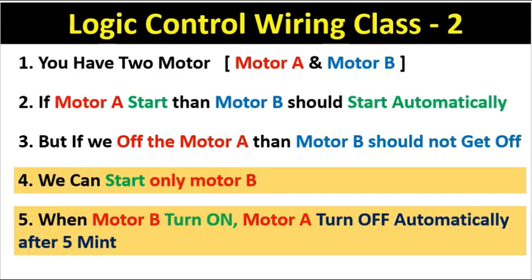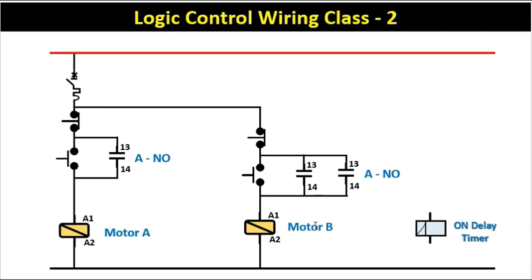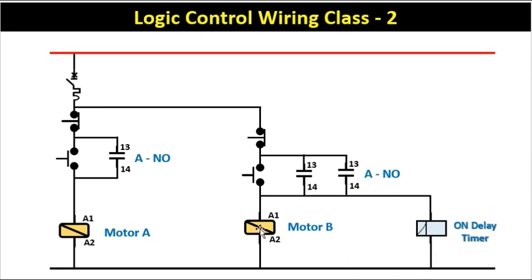Now in the conditions, if we turn on motor B, motor A should turn off. The power supply going to contactor B — we take this and also connect it to the timer. So when power supply goes to contactor B, this timer also gets power supply. I connect one more wire from this wire to supply the timer. We also connect neutral power supply to the timer. According to this circuit, if we press the start push button, power supply goes to both contactor B and this timer.